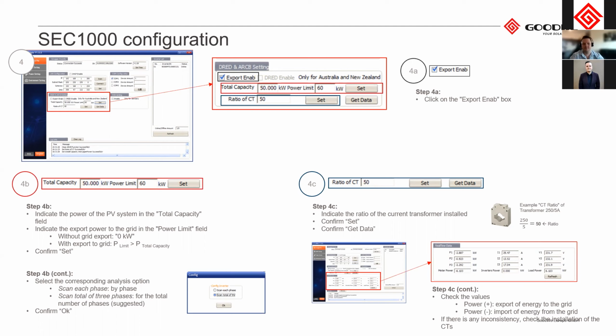So as you can see in our example, we have a 250 to 5 CT. So we just take 250 divided by 5 and that gives us 50, which is our ratio. We can then press set. No need to press the get data. Get data is only really used if we are using a GM3000 smart meter with GoodWe CTs, or if we want to see what was set previously. So if we disconnect from the logger, reconnect, and we don't see anything here, we can say get data, and then that will populate the data that was previously set on the logger.